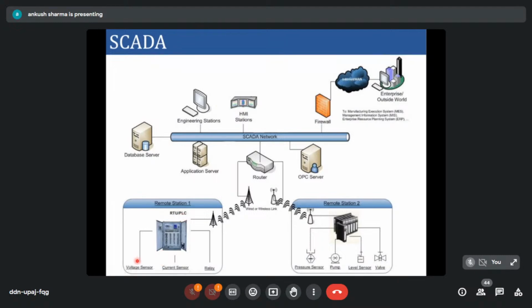In the field we have two major sensors for the power system network: the current transformer and the potential transformer. You take the measurement of voltage and current through the potential and current transformer. Those analog values come to the RTU through control wires, then get digitized using an analog to digital converter in the RTU. Then you do initial filtration of the digital data just captured, and process that information by packing it into a particular protocol, then using that protocol you send data to the remote server.